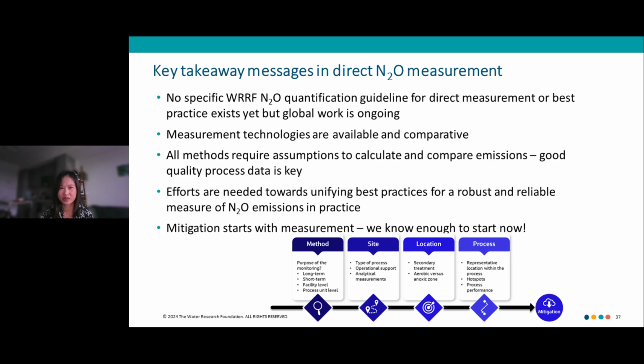So some key takeaway messages in direct nitrous oxide measurement. So far, we still don't have an industry standard or guidance on how to measure it at a wastewater treatment plant, but the global work is ongoing. Many measurement technologies are available and comparative work is ongoing. All methods require some assumptions to calculate and compare the emissions, but good quality process data is critical. Efforts are needed towards unifying the best practices for a robust and reliable measurement of N2O emissions in practice. But please do not let that deter you. We know enough to start today, and really mitigation starts with measurement.